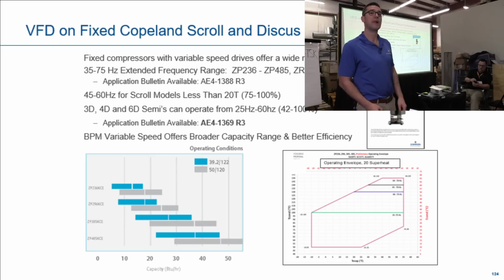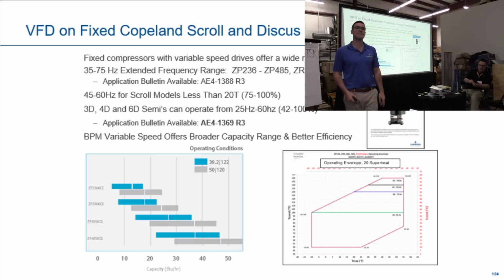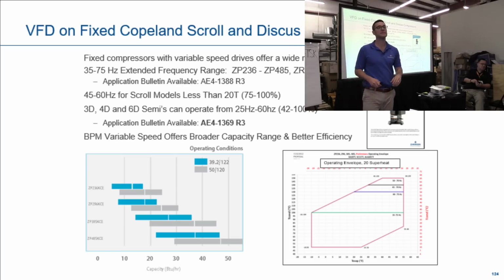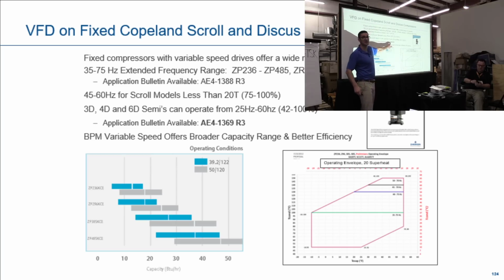Do those compressors have grounding rings for use with the VFDs? Well, I'm not sure about that question either. But I know for sure we have tested it in this range here from 25 to 60 hertz. There are no issues. Dave? Trevor, the grounding rings are typically used for ball bearing type bearings. Ours being sleeve bearing, I don't think it's necessary. Yeah, that's exactly right. Thank you, Dave. Once again, check your AE bulletin. You can automatically help your customers out and put a drive on it.